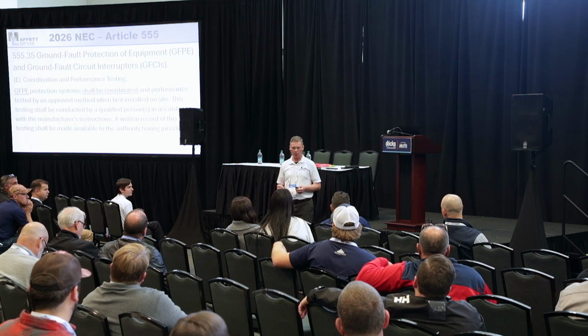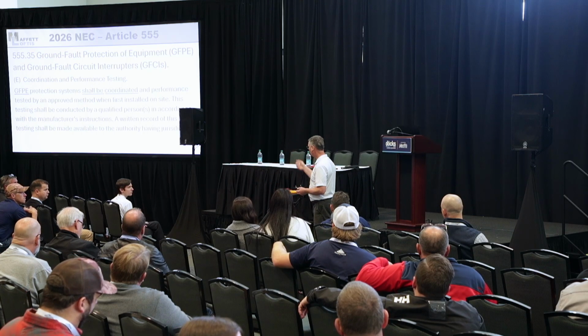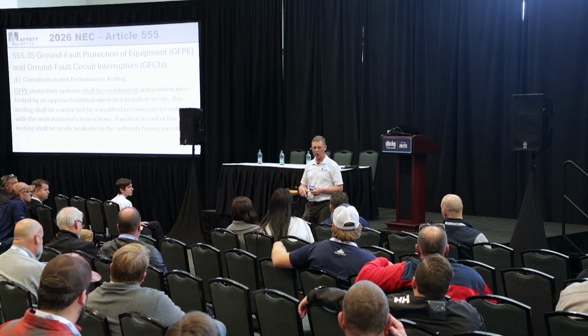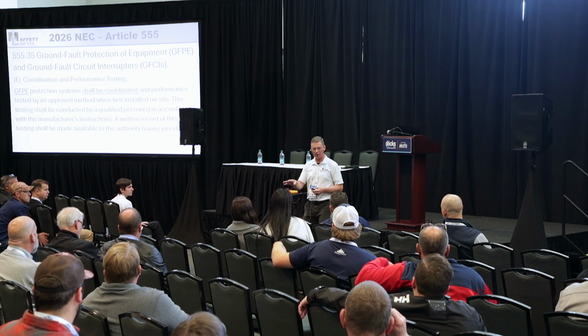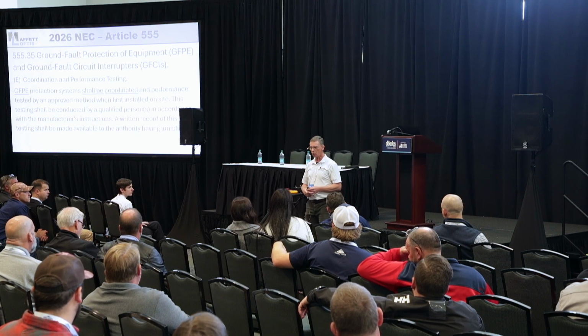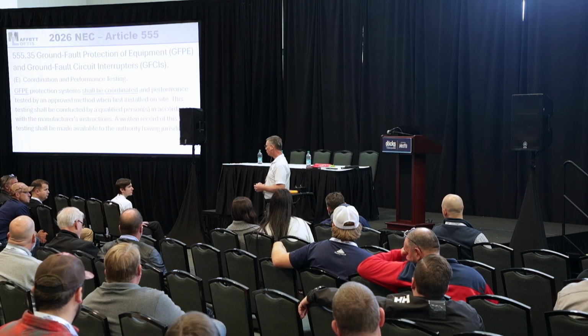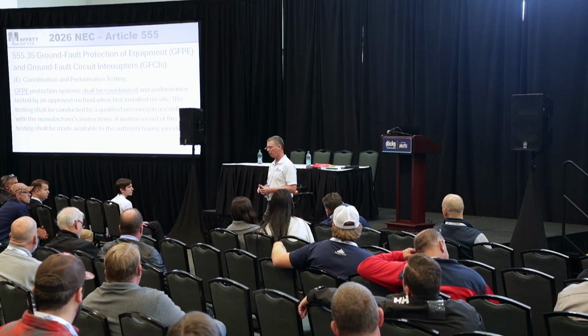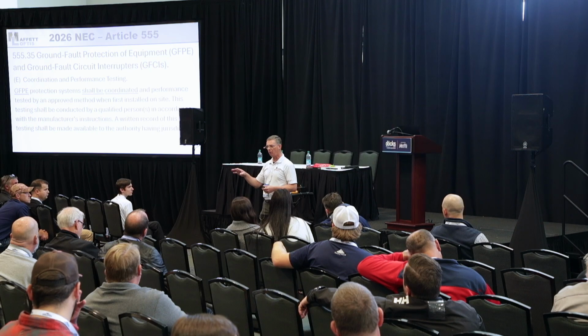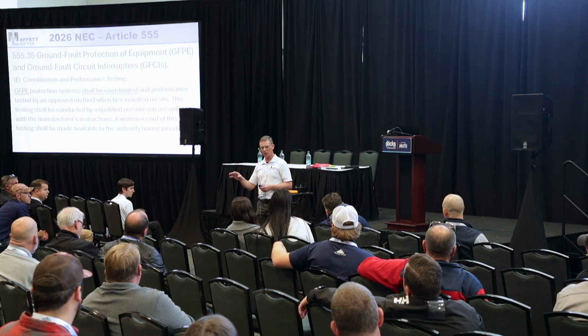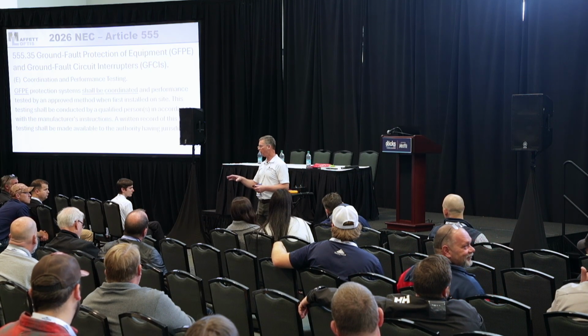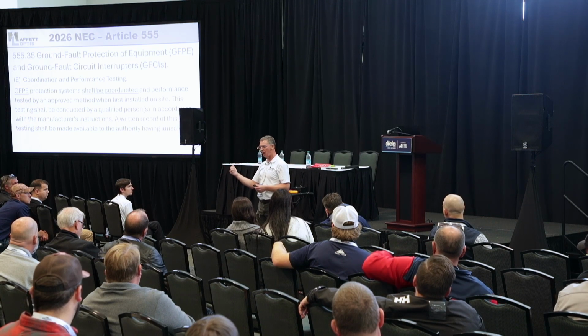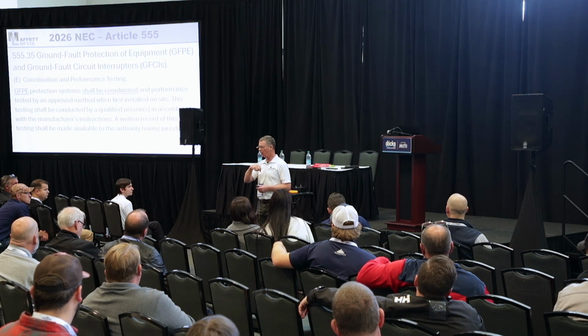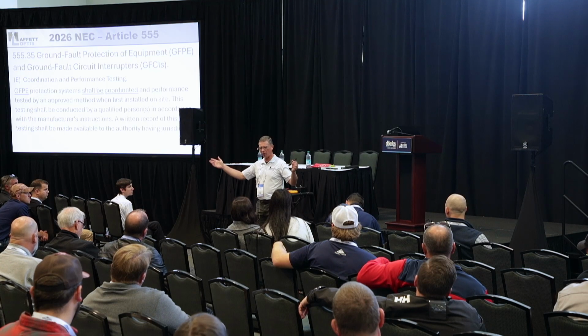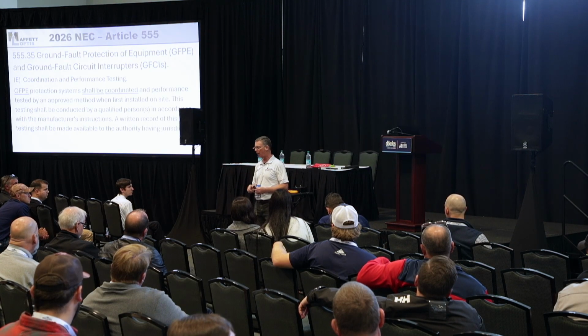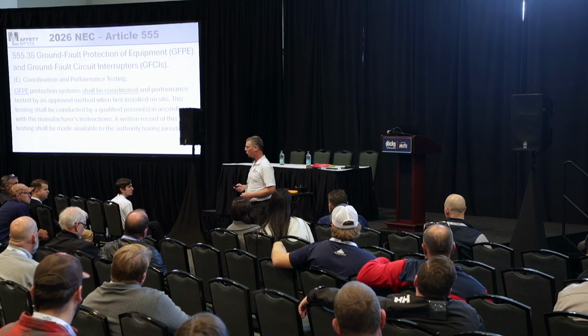Okay, it's not acceptable, and I'll show you, every marina that I design, I go out and I test, and I make sure that it is coordinated, so that there's not an issue with the GFPE systems. There's still an issue because you can still trip a boat locally, but if a bad boat comes in and wants to leak current, we only want that one receptacle that's supplying power to that boat to go dead. We don't want the neighbors to go dead, the 10 boats to go dead, or the entire dock or the entire marina to go dead because you got one bad boat. So this coordination is very important.